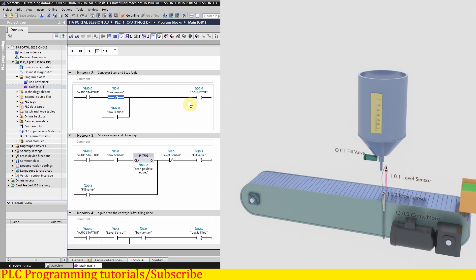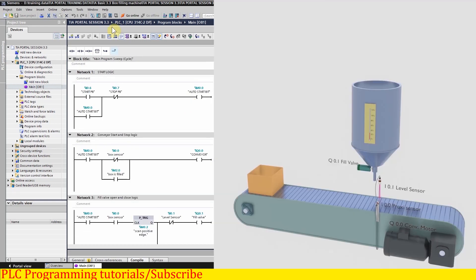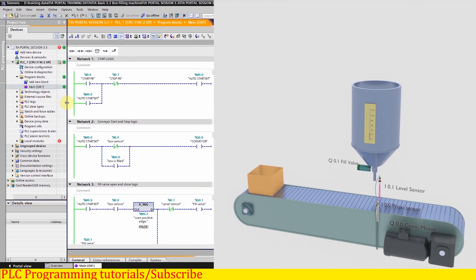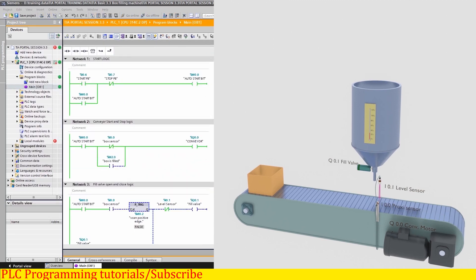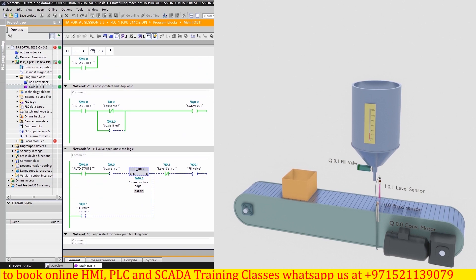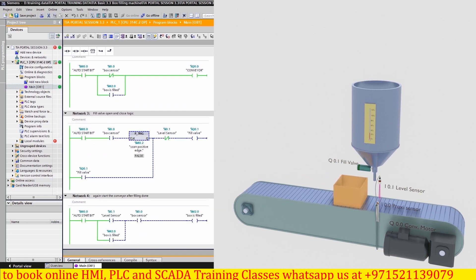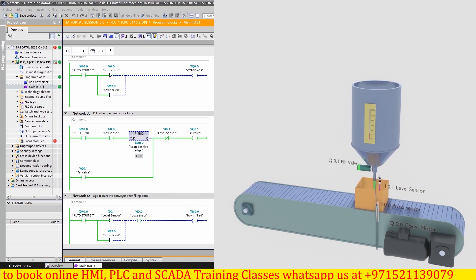We will upload this project into the PLC and see how it works. As soon as we press the start push button I 0.6, it holds on the auto start bit M 0.0 in network one. This auto start bit M 0.0 turns on the conveyor motor Q 0.0 and the box starts moving towards the filling station. As the box comes in front of sensor I 0.0, on the rising edge it holds on the filling valve Q 0.1 in network three, and liquid starts filling inside the box through the nozzle. As the liquid reaches the fill level, level sensor I 0.1 turns on and the normally closed contact of I 0.1 unlatches the filling valve Q 0.1, stopping the filling.